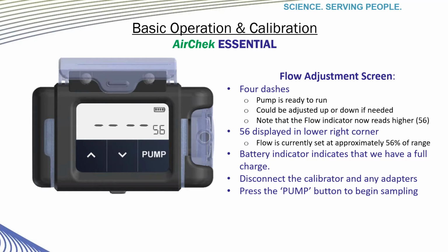We are now back at the flow adjustment screen. If necessary at this point, we could do a calibration again. If something happened and it changed and you needed to calibrate at a different flow rate, we could start that process again. We have just come back to the flow screen. But since we know that we just calibrated to our desired flow rate, we're ready to start collecting the sample.